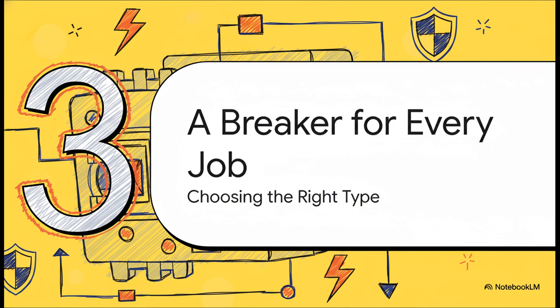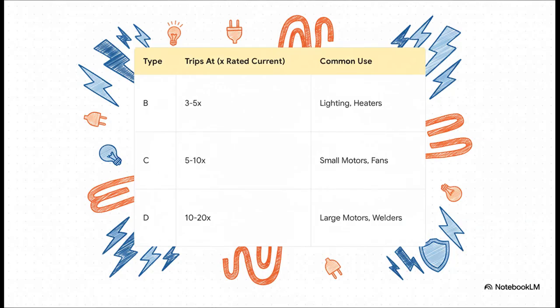Now, as you can imagine, not all electrical circuits are created equal. The circuit for your bedside lamp has very different needs than the one for, say, a giant motor in a workshop. And that's why MCBs come in different types, which are really just different levels of sensitivity. The most common ones you'll run into are types B, C, and D. A type B is your standard household breaker for things like lights and outlets. It's pretty sensitive. It'll trip if the current gets just 3 to 5 times its normal rating.